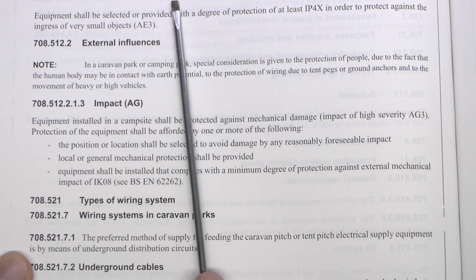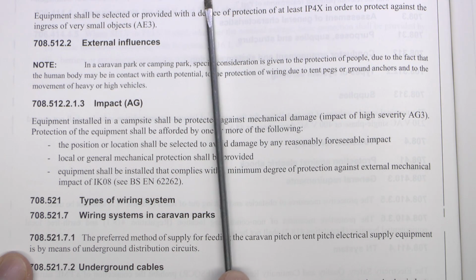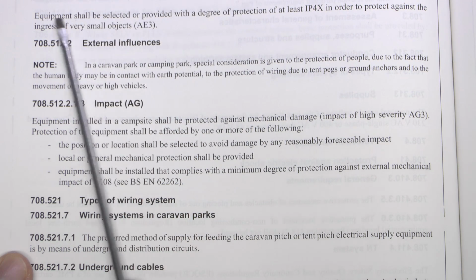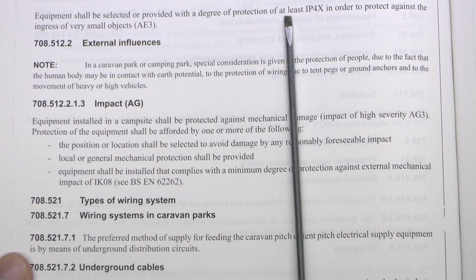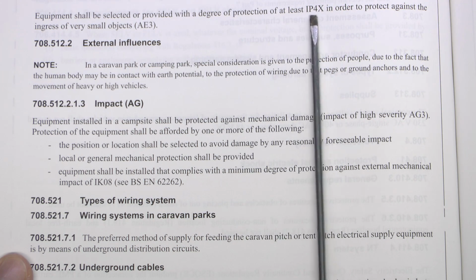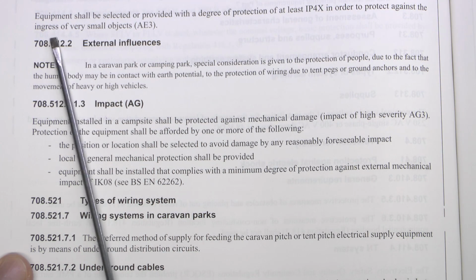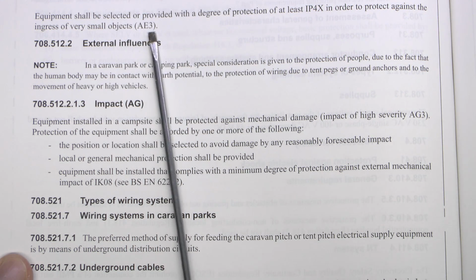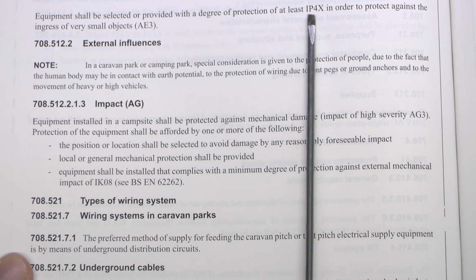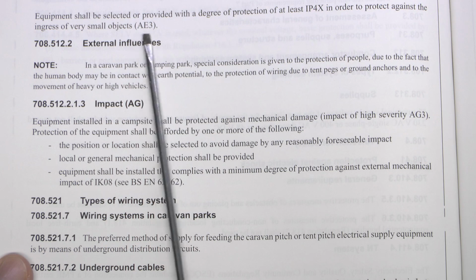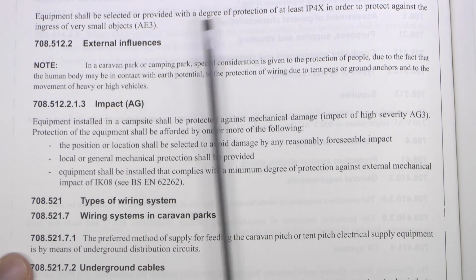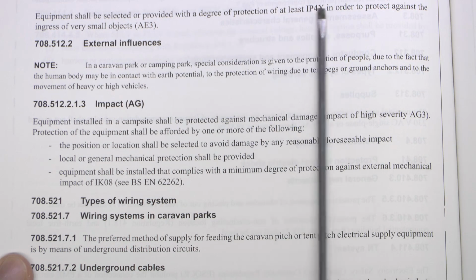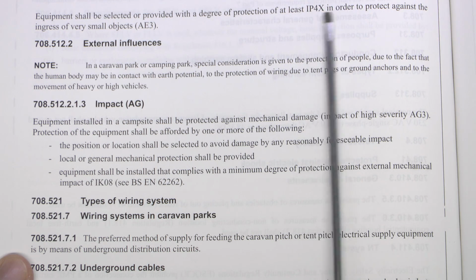708.512.1.2, which is presence of solid foreign bodies, and that's now AE. And the change here is that it's now a degree of protection of at least IP4X and protecting against the ingress of very small objects, as in AE3. Previously this was IP3X and it was AE2, which is small objects, so essentially it's moving up in the protection there to basically the next level.